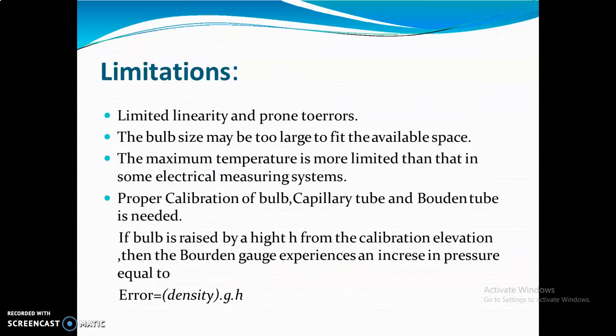The limitations include limited linearity. The bulb size may be too large to fit the available space. Proper calibration is required. If the bulb rises in height from the calibration elevation, then the Bourdon gauge experiences increasing pressure equal to error rho g h.